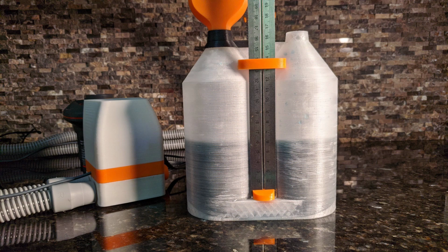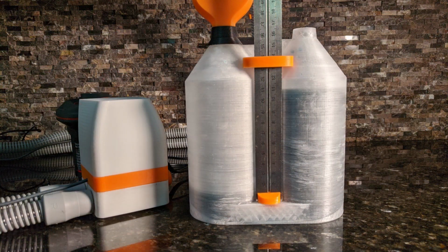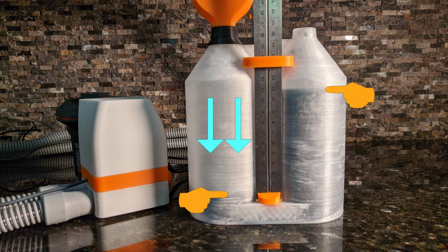Although we need a test lung for official ventilator calibration, the price of even the simple spring-loaded products were beyond our budget. However, we did not want to sacrifice pressure or volume accuracy. Fortunately, there is a simple and indisputable alternative which requires no calibration and is the baseline for which test lung products are measured. Maybe you took high school physics? You might even remember Pascal's principle. If not, it's real intuitive. Water always maintains the same level in a connected vessel. Pressure applied to one side causes the water to rise on the opposite side. Since the medical industry uses units of centimeters of water, it makes it very easy to illustrate using food coloring dyed water. As can be seen here, the relative heights of the water gives the exact pressure being applied.